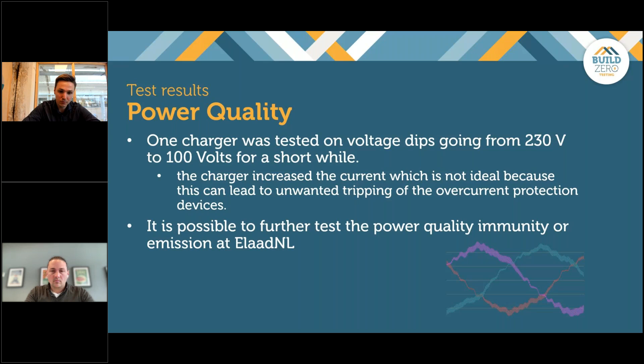In this test, we saw that some of the chargers increased the current on one of the phases. This is unwanted, because if the current is increased, the protecting devices can trip and your charger is powered off, which you don't want. ElaadNL tests power quality for all kinds of chargers, and we advise you to do that before entering the field, because the grid connection at the construction site is not always ideal.